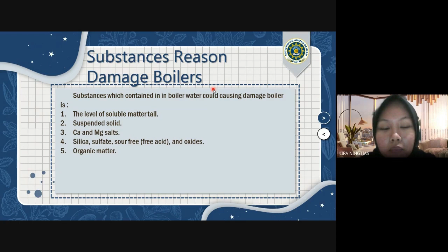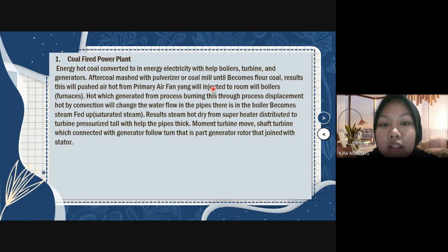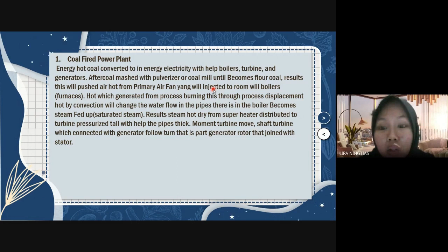Application of boilers in industry. One, coal-fired power plant. The energy of hot coal is converted into electrical energy with the help of a boiler, turbine, and generator. After the coal is ground with a coal mill until it becomes flour coal, it is pushed by hot air from the primary air fan into the boiler furnace, generating heat from the burning process. Through heat transfer by convection, the water in the pipes inside the boiler changes into saturated steam. The hot dry steam from the superheater is distributed to the turbine under pressure with the help of pipes. When the turbine moves, it is connected with the generator, which turns the generator rotor joined with the stator.